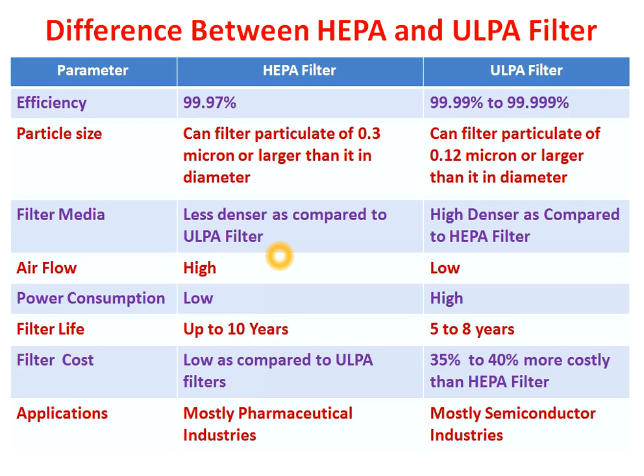This table represents the basic difference between HEPA and ULPA filters. One column represents the parameter, the next is for HEPA filter values, and the other is for ULPA filter values. The first parameter is efficiency: the HEPA filter has an efficiency of 99.97%, whereas ULPA has 99.99% to 99.999%. That means the ULPA filter has higher efficiency compared to the HEPA filter.